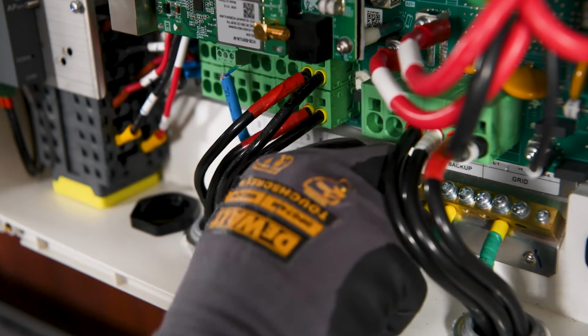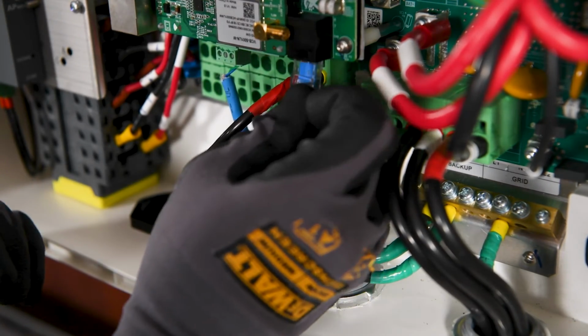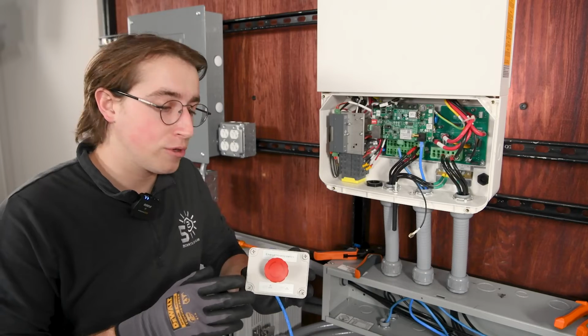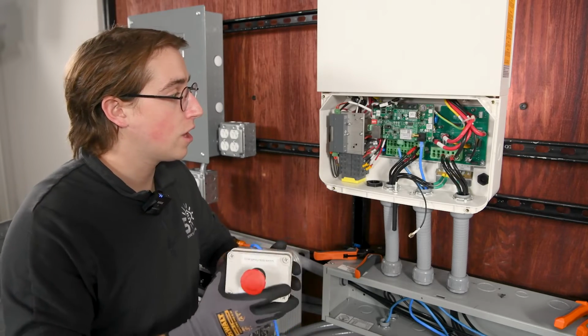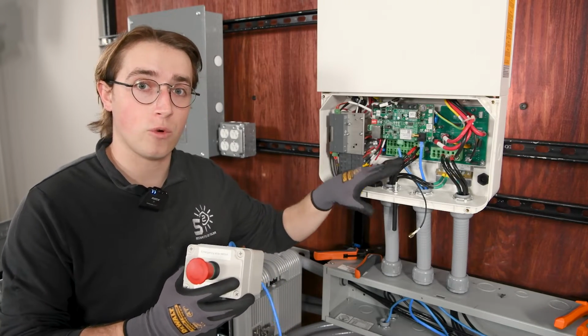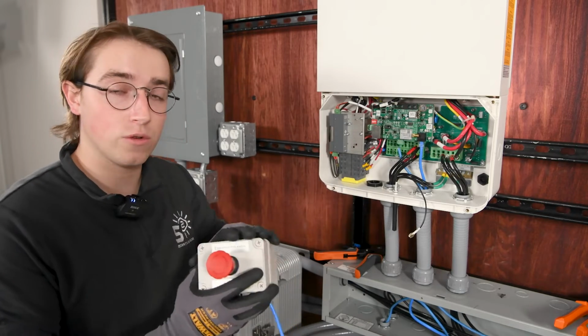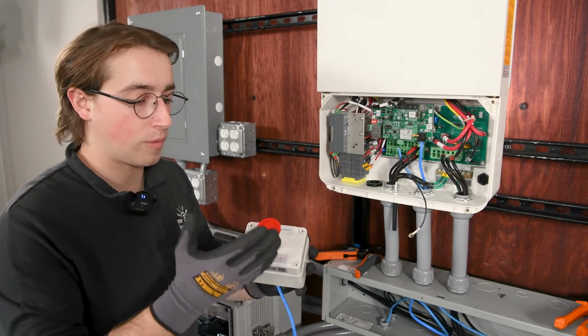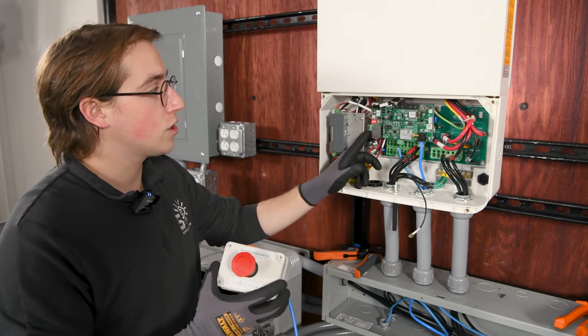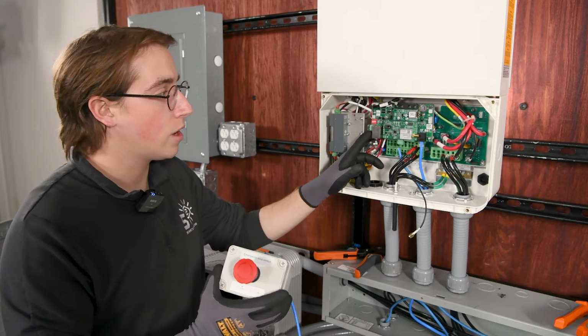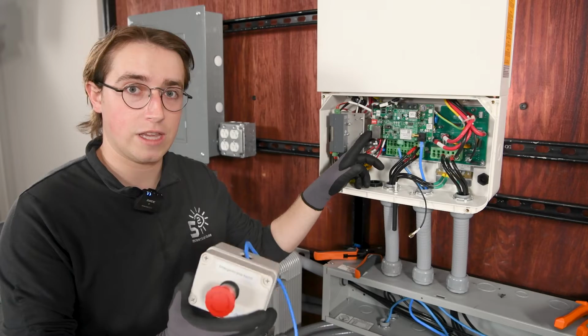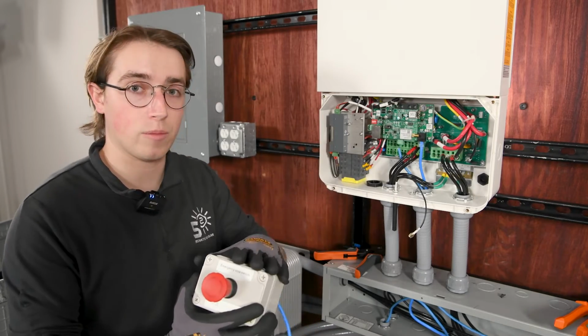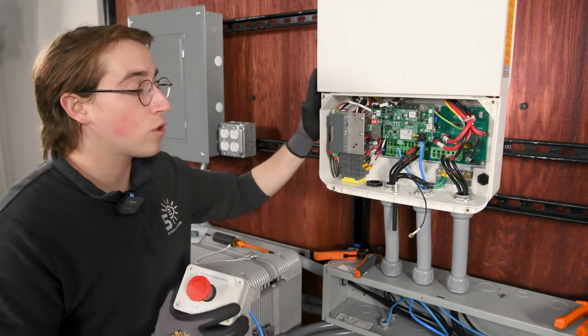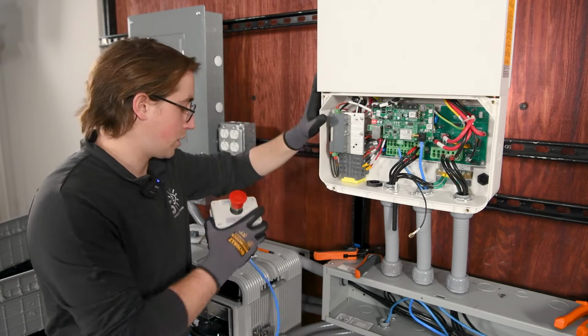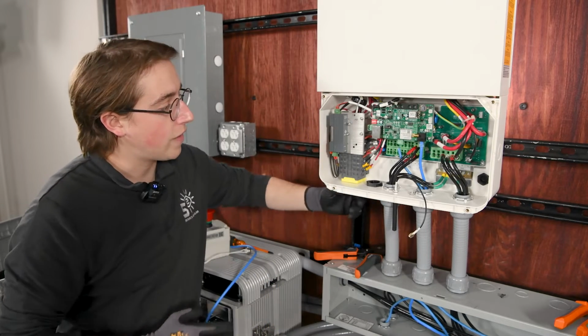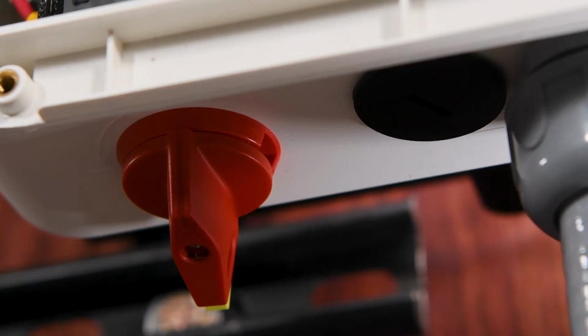Like so. We're going to walk through just a few more components that you can install with the 11.4 inverter before we actually connect our power sources. One is going to be our rapid shutdown button, or our rapid shutdown initiator, and this is actually going to connect to the 3-pin connector here, and this is a normally closed circuit, or a keep alive signal, that will actually be wiring up through the rapid shutdown. The 11.4 also has its own built-in RS initiator, a rapid shutdown initiator, and that's on the bottom, and it's just a little switch that you turn.